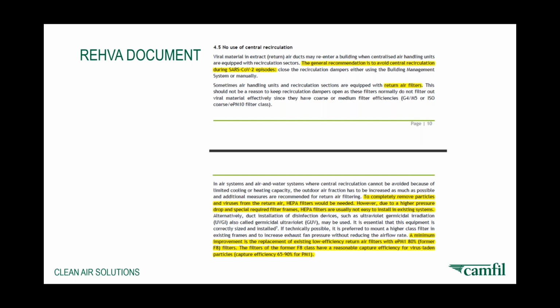If you cannot get a HEPA into the system, it's recommended that a minimum improvement would be the replacement of the existing low efficiency return filters with at least an ePM1 80%, so the former F8 type filter. And this will give you an approximate capture efficiency of 65 to 90% for PM1, which is particles of 1 micron. Not great at very, very low particle sizes, but the best protection you can get in an HVAC system.